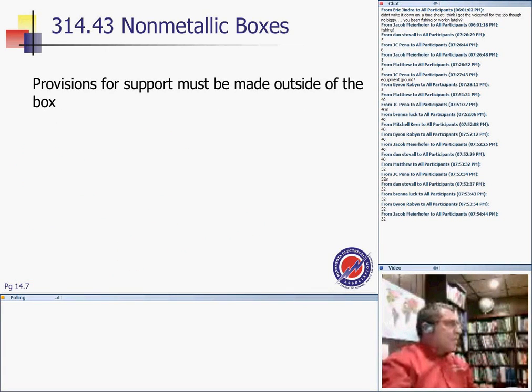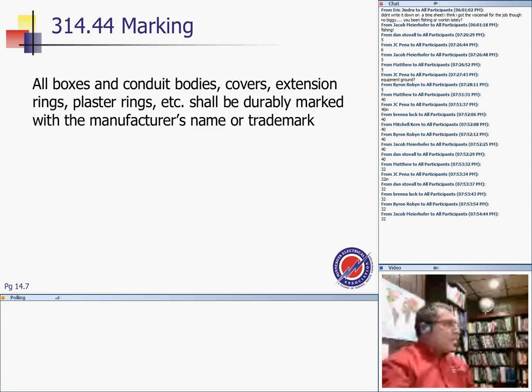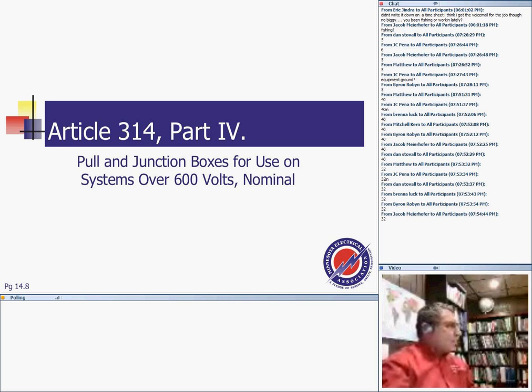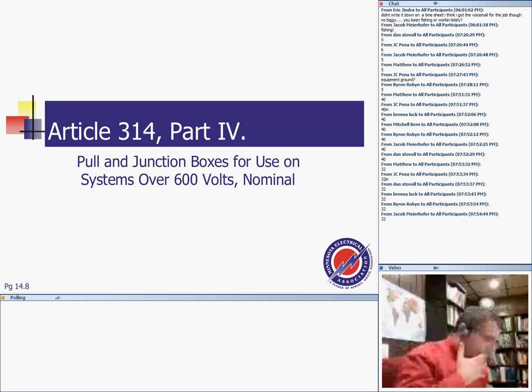Non-metallic boxes, provision for support must be made outside of the box. All boxes and conduits shall be durably marked with the manufacturer's name or trademark. And that's it in terms of conduit, guys, before we move into part 4, which talks about high voltage.